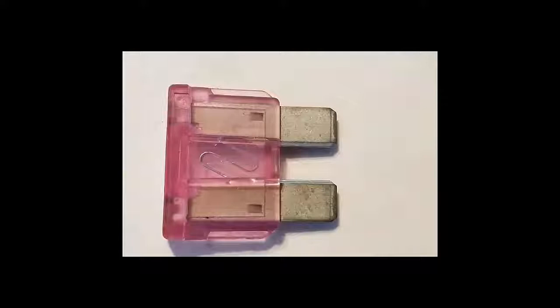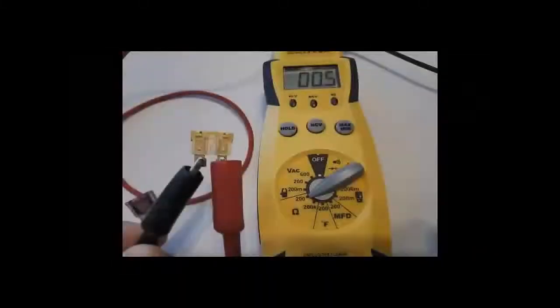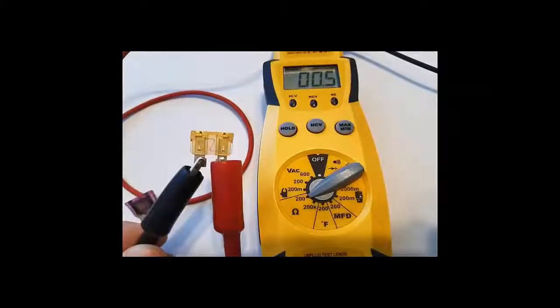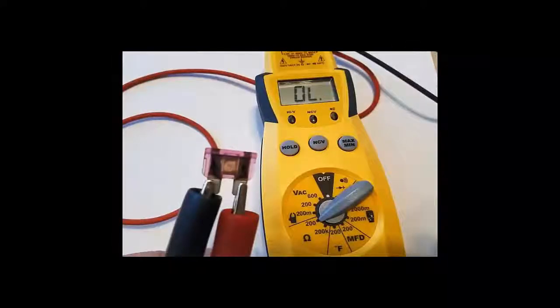The easiest way to check it is to pull it out and look at it. See the thin element in the middle? It should be intact and there should be no discoloration in there. If the fuse is bad or is blown, the element will be broken and there will usually be black discoloration in there also. You can check this fuse by hooking it to an ohm meter while you have it pulled out. If it is good, your meter will indicate a closed or complete circuit. If it is bad, your meter will indicate an open line, as shown by OL on the meter I'm using. As long as we are discussing low voltage, this is a good time to talk about the transformer.